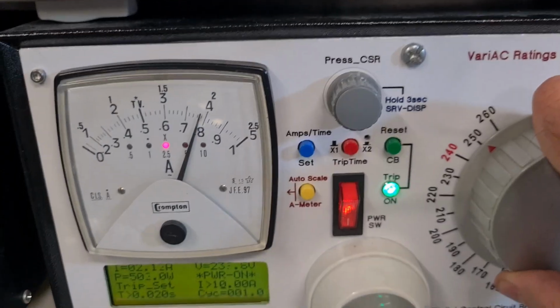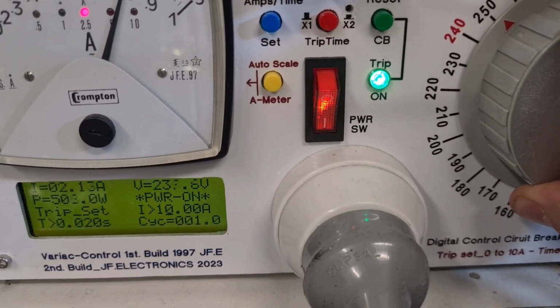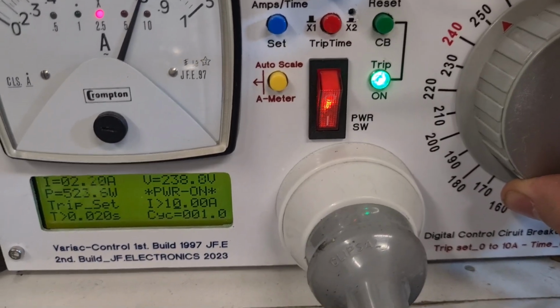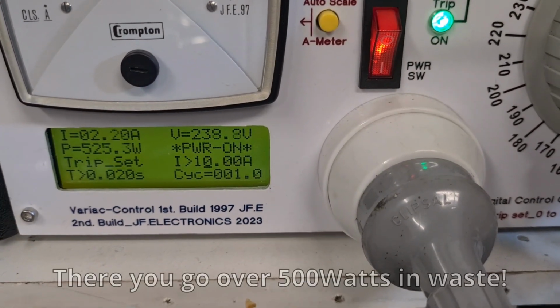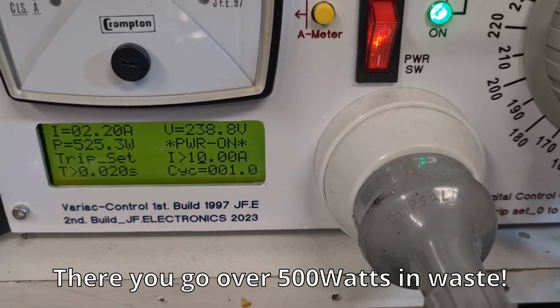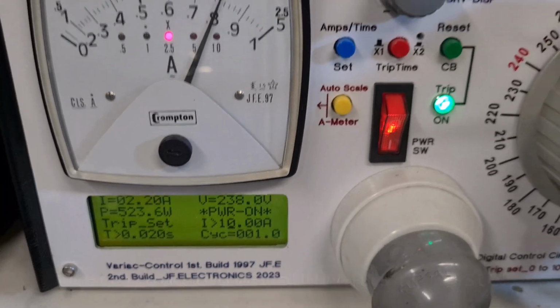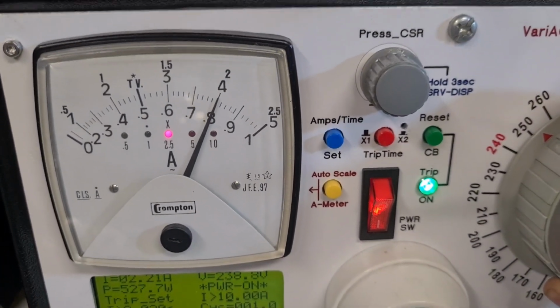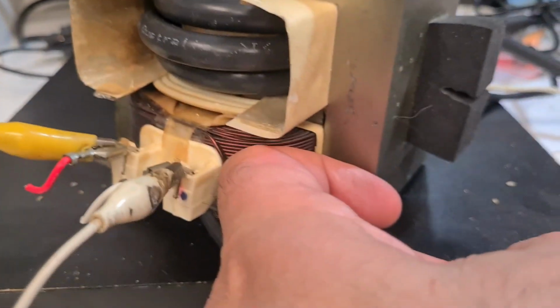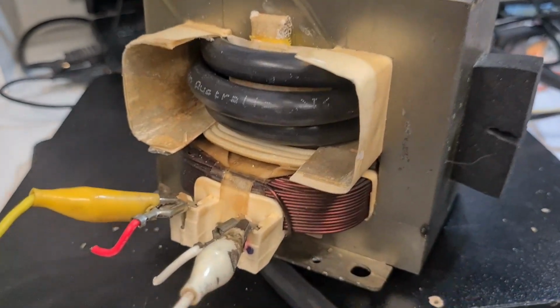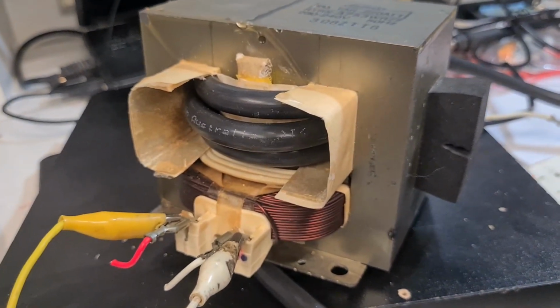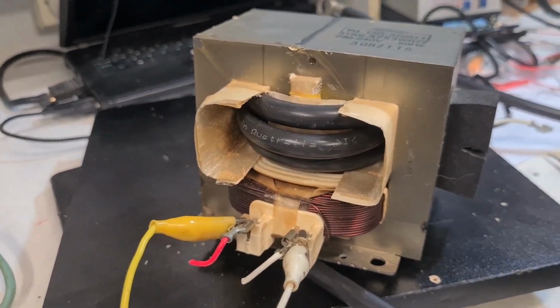Okay, so at around 240 volts, it's actually over 500 watts, just an idle current. So it's taken 2.2 amps, or 2 amps. And you can see the secondary is open, and there's no power generated on the secondary. And of course I have tested this in this way, and the windings at 2 amps still run very cold. So it doesn't actually heat up, but it does draw 2 amps.